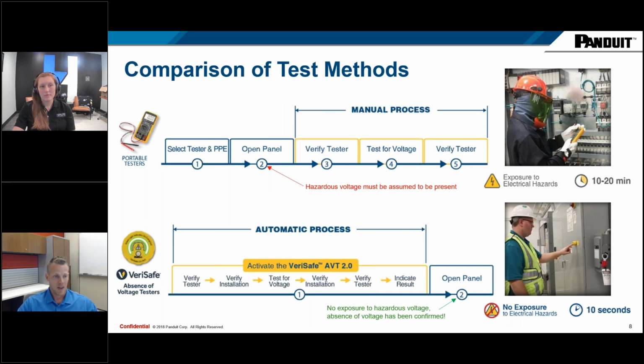So with absence of voltage testers, it runs through all the series of tests from the outside with the panel door closed, and you're not opening that panel until you've already confirmed that there is no hazard present inside the enclosure, right? So at that point, there's no exposure to electrical hazards, no more than if you were just to walk by the cabinet with the door closed. That process really takes like 8 seconds, but we call it 10 seconds just for easy mental math there. Quite a bit of a reduction in time.